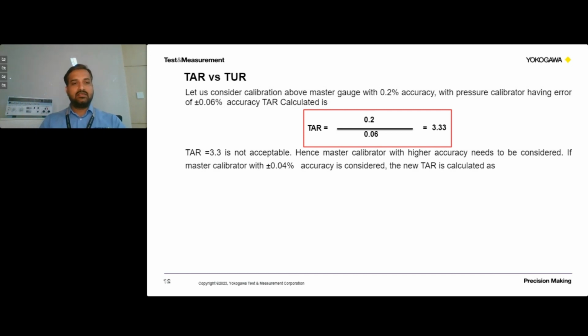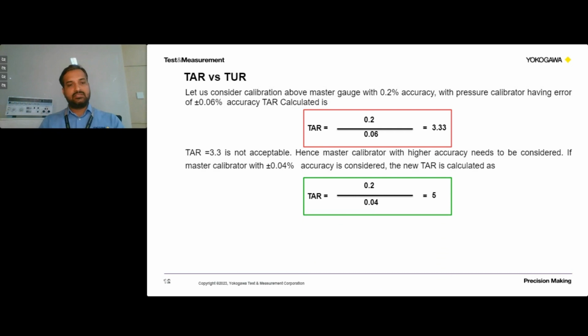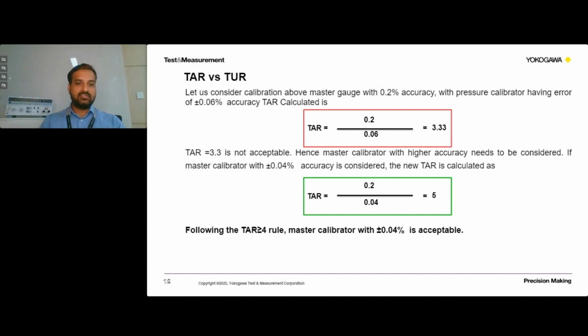So we are considering the pressure calibrator which is having 0.04 percentage of accuracy. So here we are meeting the basic requirement of 1:4 ratio. And hence this pressure calibrator with 0.04 percentage of accuracy is acceptable, whereas 0.06 percentage of pressure calibrator is not acceptable.